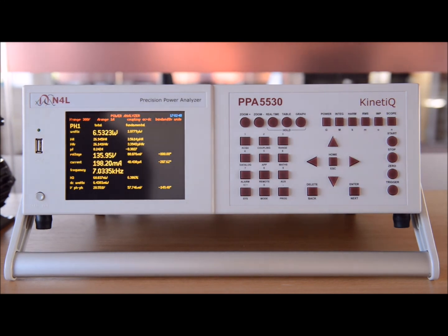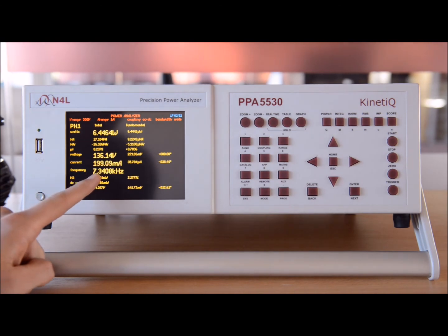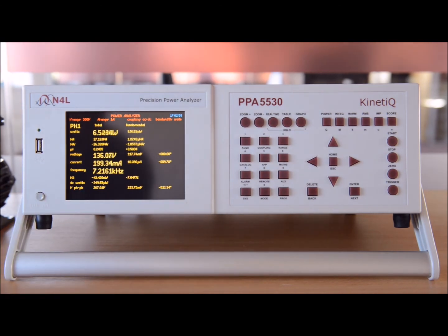Right, so what we have here is the output of the AC drive, and we can see the 7.4, 7.3 kHz switching frequency being locked onto. The reason for that is because the instrument's just in default settings, so we're going to go through every setting required in order to get a reliable, stable and accurate PWM measurement of this drive. So a power measurement of this drive. Let's have a quick look at the scope.